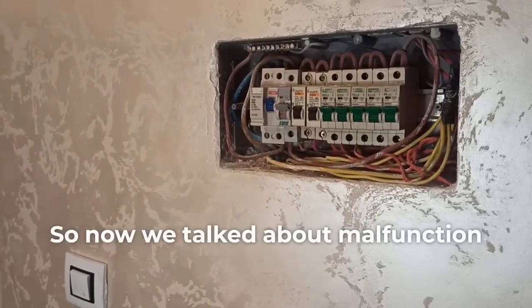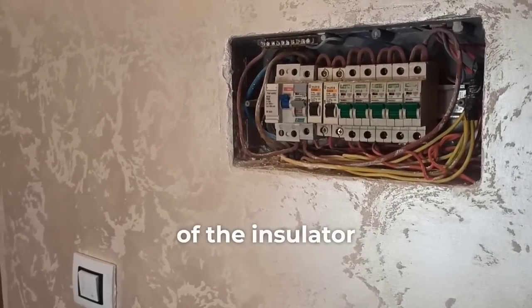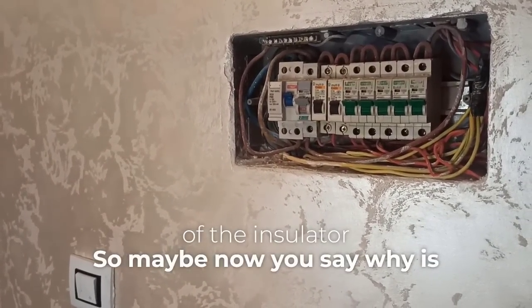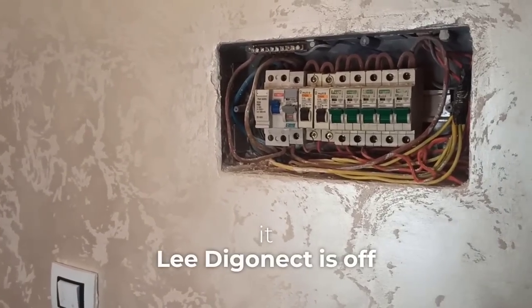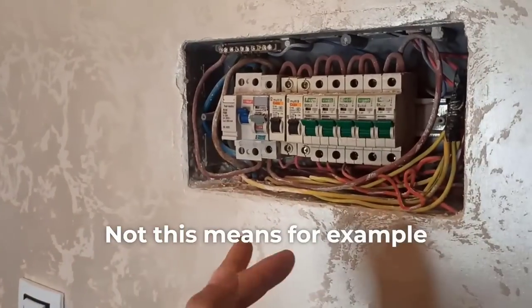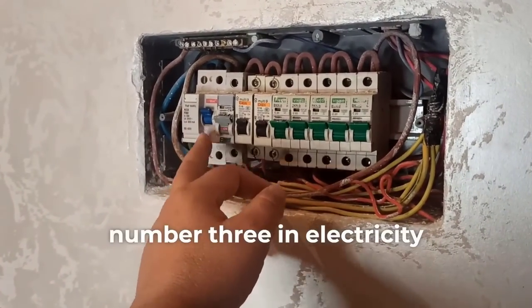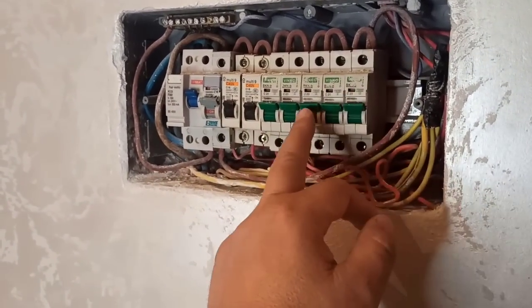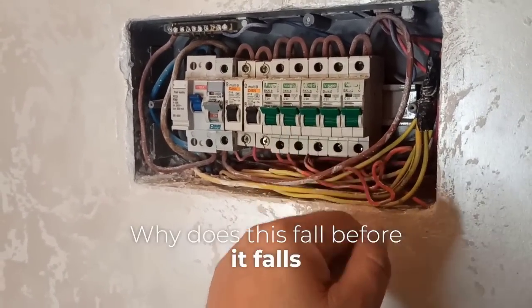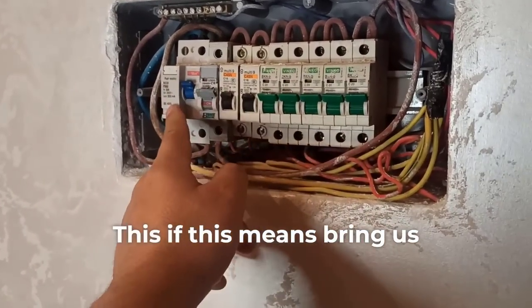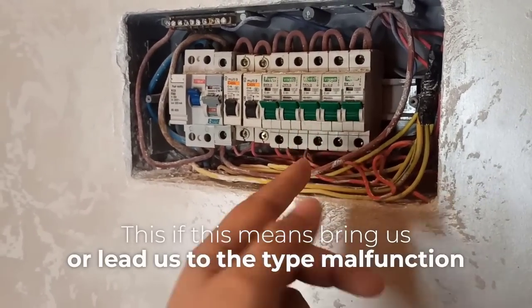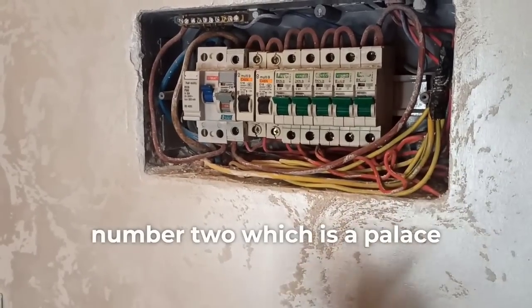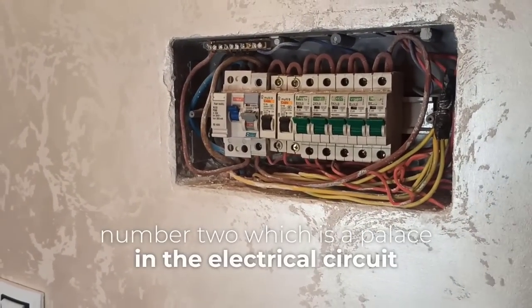So now we talked about malfunction number 1, which is the loss of the insulator. So maybe now you say, why does the differential breaker trip? This means, for example, I have a problem in circuit number 3 with electricity leakage. Why does this trip before the sub-breaker trips? This leads us to malfunction number 2, which is a short circuit in the electrical circuit.